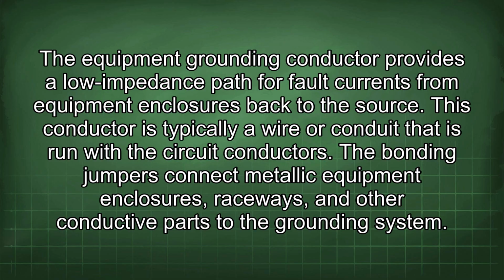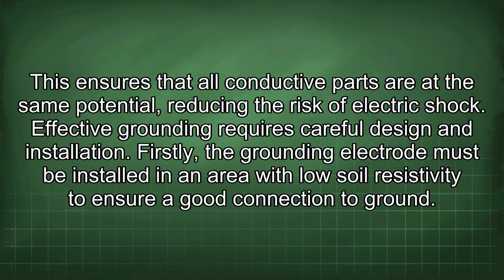The bonding jumpers connect metallic equipment enclosures, raceways, and other conductive parts to the grounding system. This ensures that all conductive parts are at the same potential, reducing the risk of electric shock. Effective grounding requires careful design and installation.